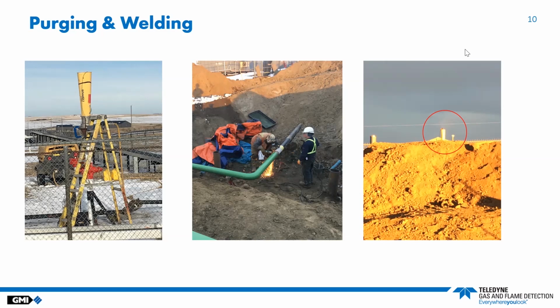Welding smoke exhaust is identified as a contaminant to gas detection technology, as there are small particles that can inhibit the sensor performance outside of the use of infrared technology. It is always best practice to replace filters often and ensure that you capture small particulate found in the welding exhaust to prevent damage to them. These are captured using specialized filters designed to capture small particles outside of your dust and dirt, covered by the standard filtering provided by GMI.